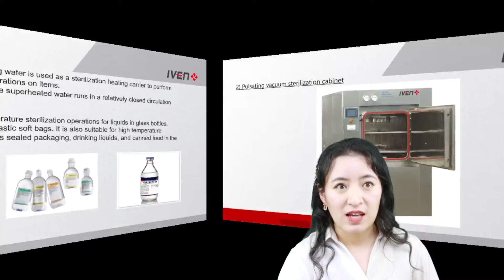Second type of cabinet I would like to introduce to you is the pulsating vacuum sterilization cabinet. The principle of this product is using saturated steam as a sterilizing medium and taking advantage of its physical characteristic of releasing a large amount of latent heat and humidity when condensing. In a certain constant temperature time, the main component of the bacteria is hydrated and solidified to be killed.